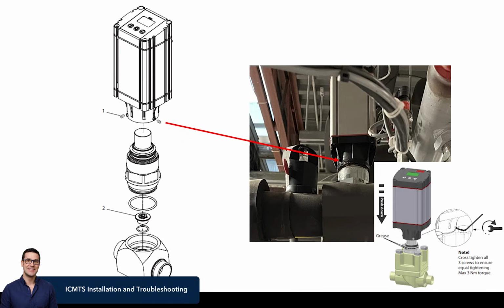So even in a horizontal position, you're really running the risk of that actuator coming loose over time and not being able to drive the valve open and close. So we do want to see that mounted in an upright position on the rack. And it has to be level. I've seen some on angles before where a lot of condensate got inside and started to rust them up. So insulation is important as well on those. Yep. I can't say I've seen a rack where it's not insulated around the valve body. So yeah, I agree with you on that part.